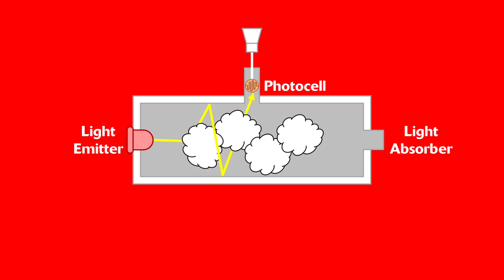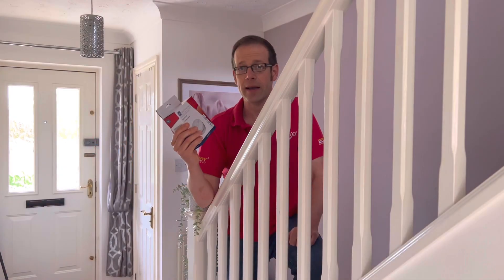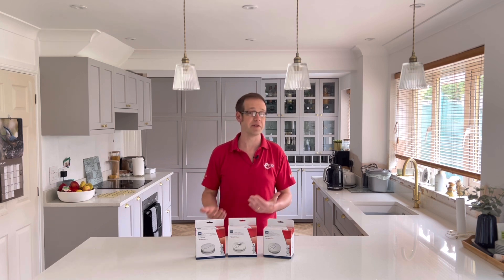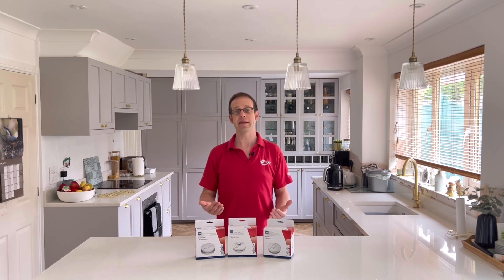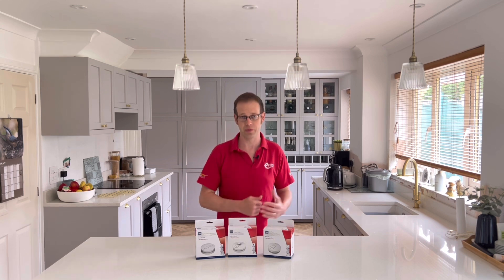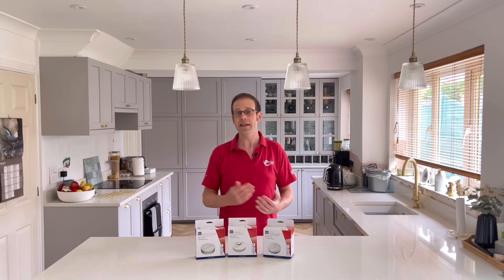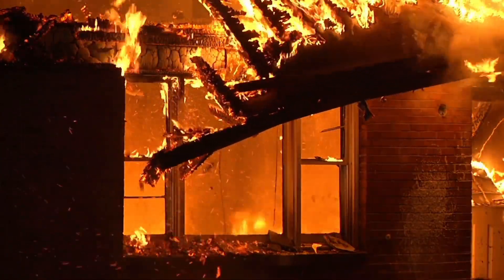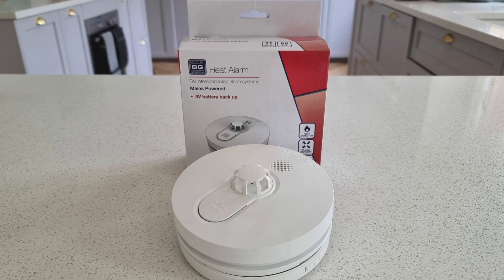This type of fire detection is eminently suitable for most spaces in a domestic setting, though there is one key area of risk. It's very important to avoid triggering false alarms for two main reasons. First, if an alarm constantly goes off when there is no fire, it may lead the occupant to disconnect the detector, meaning there's no alert should an actual fire occur. Also, the person may hear the alarm so often that in the event of a real blaze, the alarm is passed off as another false start and simply ignored. One way to avoid false alarms is by using heat detectors in areas where a smoke detector could be incorrectly triggered.